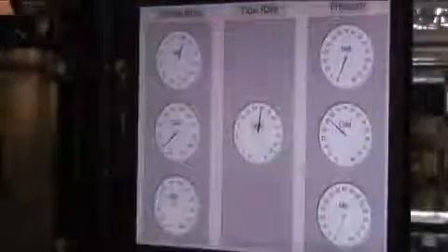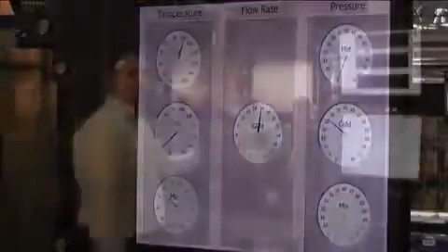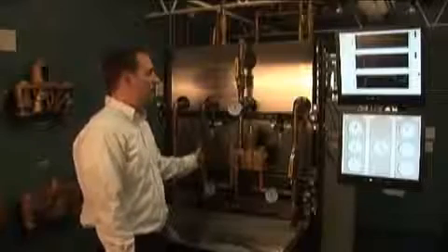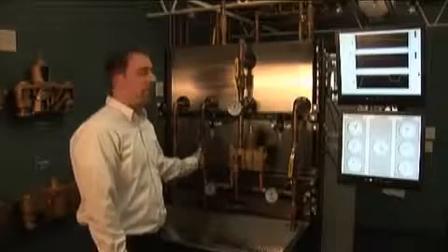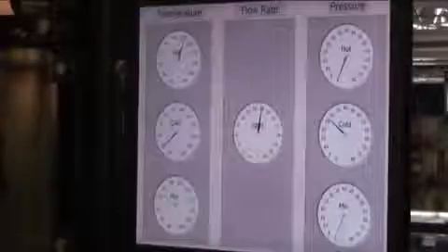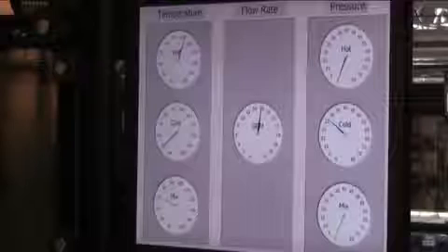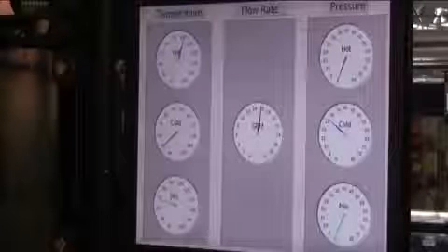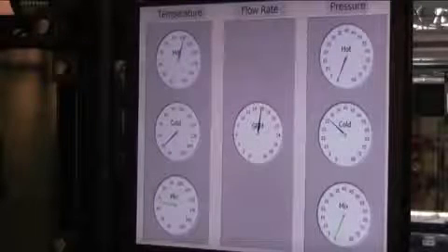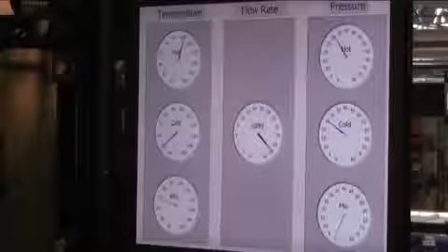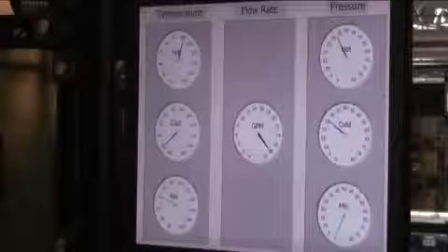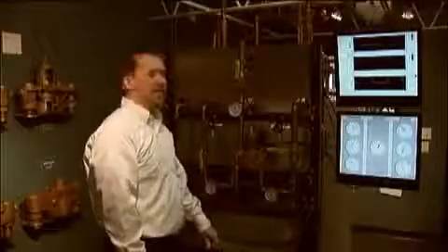If the hot water is lost for any reason, we have an immediate supply of cold water still available. This is through a fixed cold water bypass built into the valve. We don't regulate how much cold water flows through the valve. We simply regulate how much hot we add to the cold. And by doing so, we don't have any mechanism that has to move to allow full cold flow. So no matter what the situation, you know you're going to at least get cold water through the Bradley thermostatic mixing valve. If the cold water is lost, the valve will sense this.